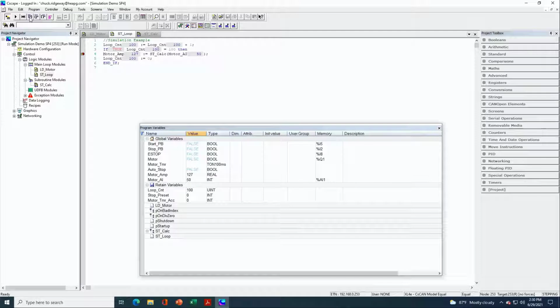The next step is to enter the subroutine. Now if I press this step in button, it's actually going to step me into the subroutine. So here we are, that's the structured text calc subroutine. Literally, as I press this step in button, I can work my way through the subroutine, and it will execute and then return back to the line after the point where the subroutine was called, which is what it's done here. Okay, very good. Now let's do a complete cycle through. Now we're sitting again with another full cycle where we went through and got our loop up to 100.